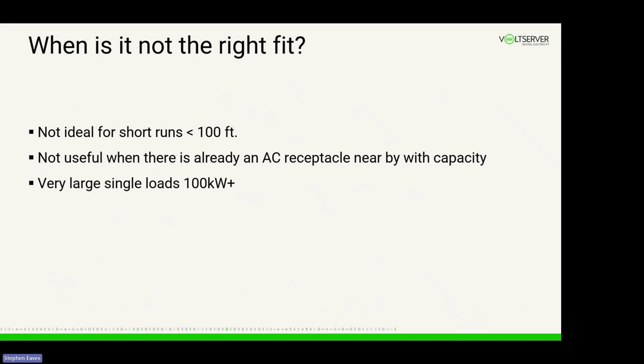In a stadium, for example, conduit installations are about $38 a linear foot, while digital electricity installations are less than $10 a linear foot. So if you go enough linear feet, you pay for the equipment and it works out very well. It's not really for very large single point loads, although we're looking at things like powering HVAC units on the top of a building. But if you have a giant motor in one place, it's probably not the right thing.